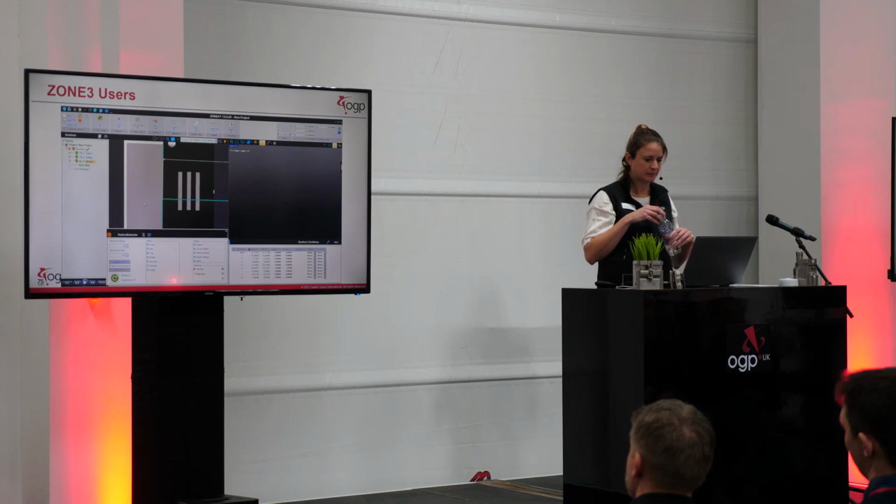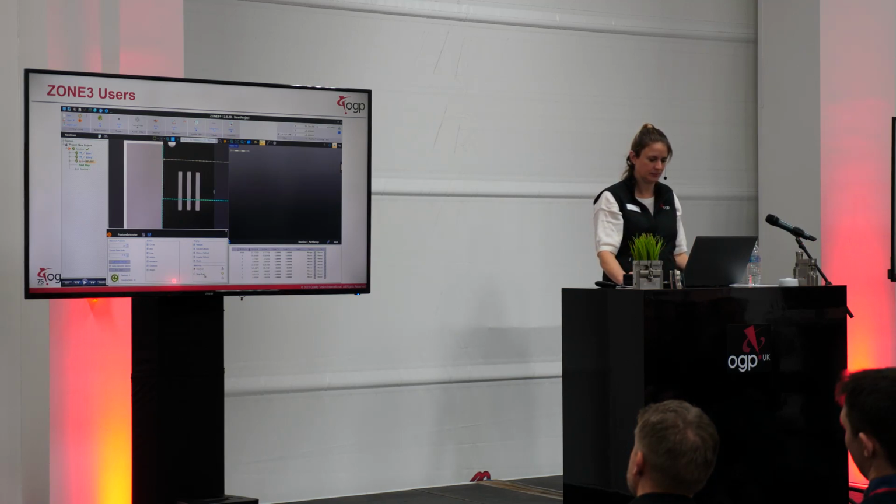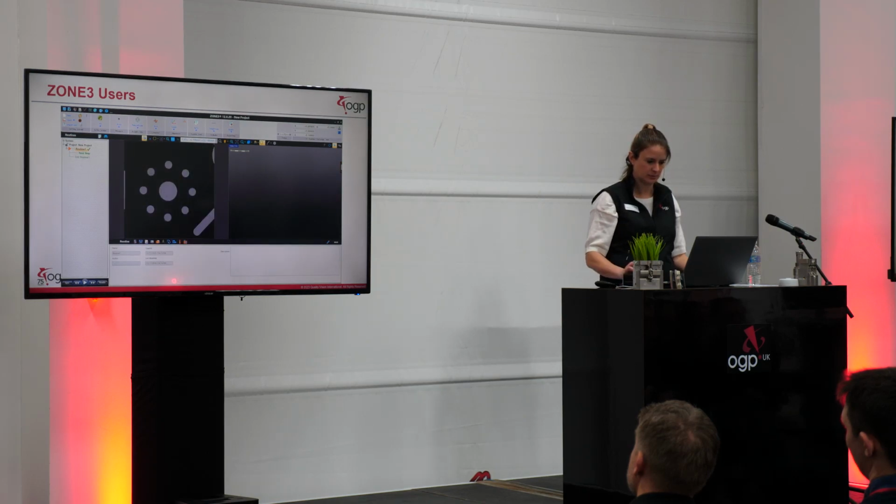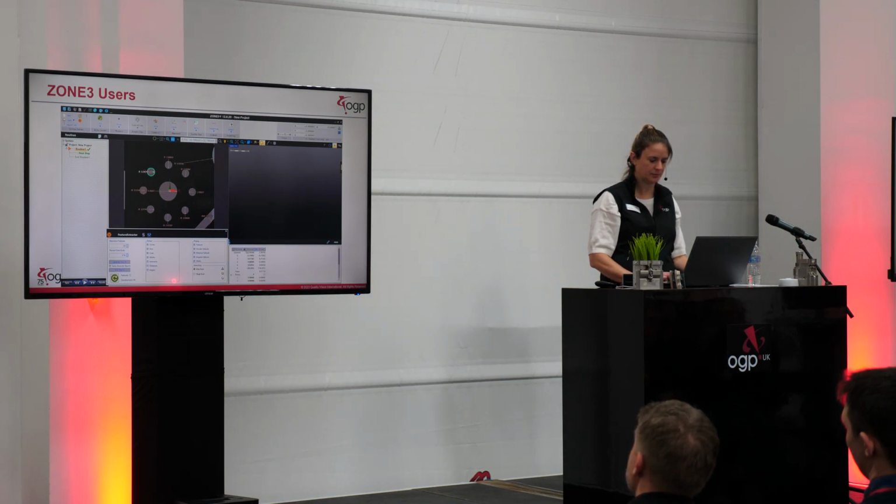Extracting across multiple fields of view can also be done automatically. An area scan allows you to configure a known region of the machine stage to extract features from. A stage scan will cover the entire measurable area and extract all features that can be seen. If using Feature Extractor for programming, once you select a feature, you can enter in nominal information before adding steps, so that it doesn't have to be done afterwards.